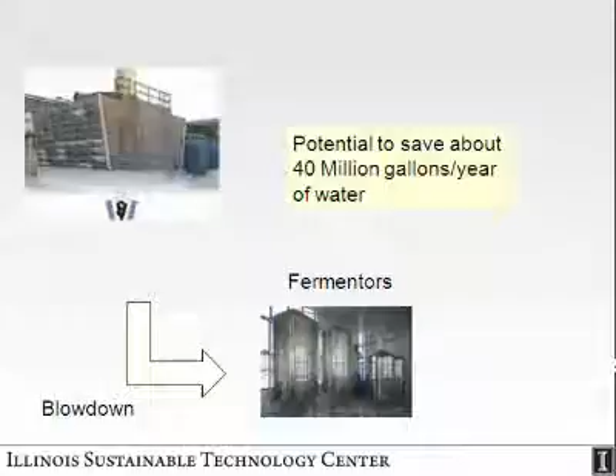Here's a different way of rearranging the process blocks within the plant, for combining other wastewater streams, such as the backwash and the RO reject. I'll take my cooling tower water and actually put it through a reverse osmosis system, purely for schematic purposes. So I basically purify this cooling tower blowdown, put it through an RO, and get an RO reject that is fairly high now in TDS.